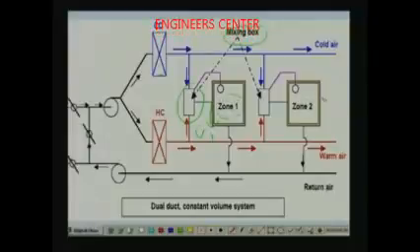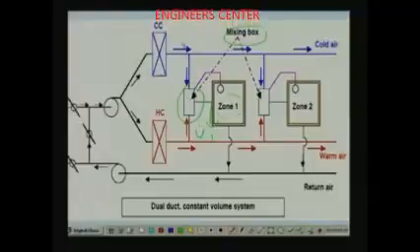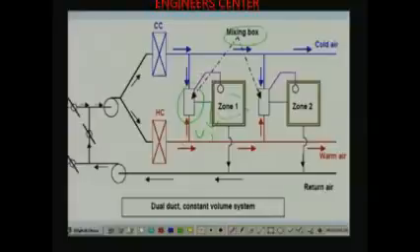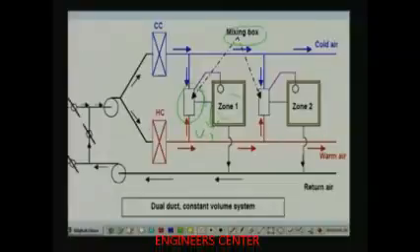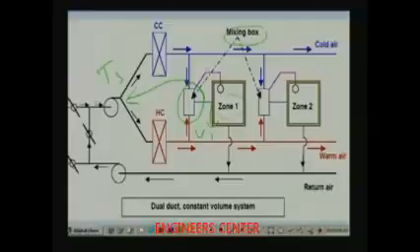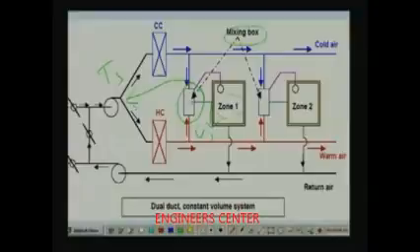Similarly for zone 2, zone 3, and so on. What we are doing essentially is cooling and heating air in two different streams and mixing the air in different proportions depending upon the load of that particular zone, supplying that air at a constant volumetric flow rate to each zone. The volumetric flow rate remains constant but the supply temperature is varied by varying the position of the mixing box, which is in turn controlled by the zone thermostat.